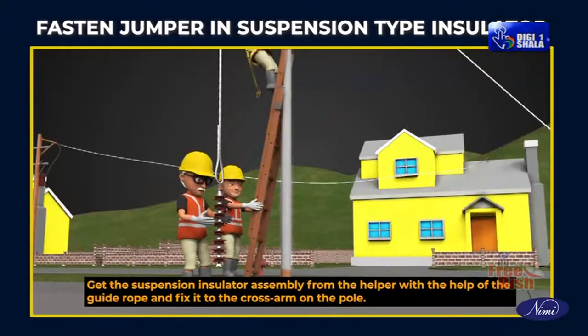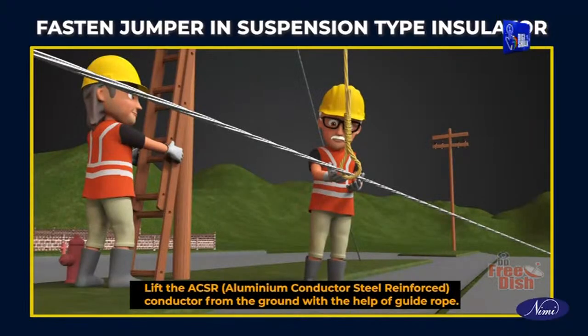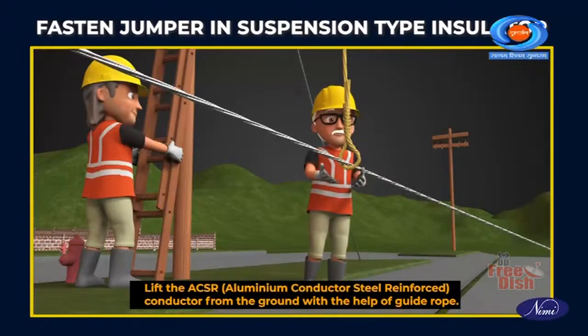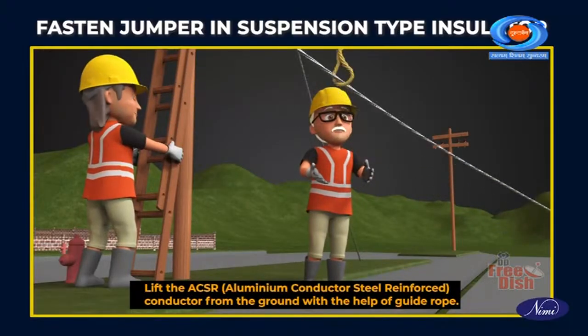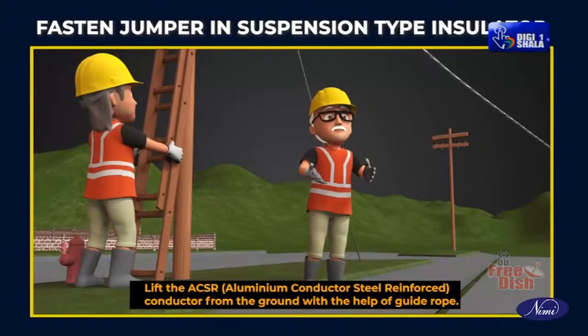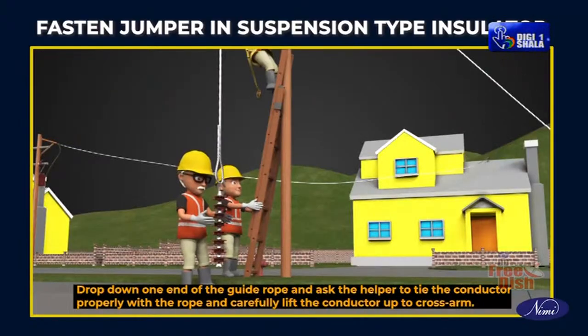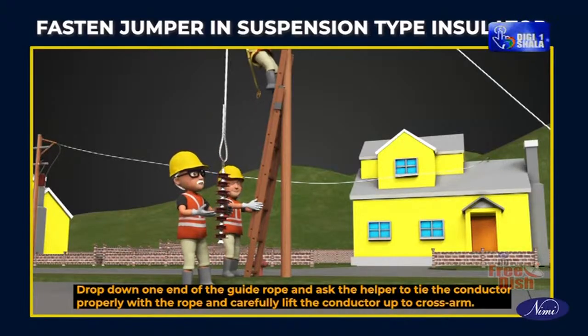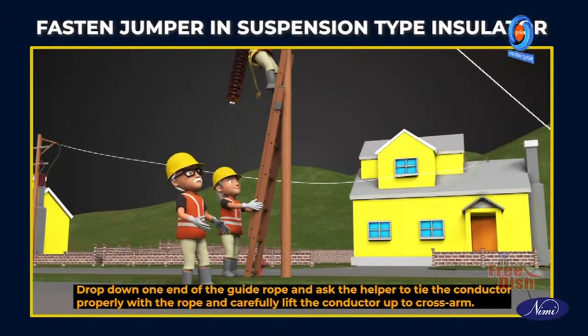Get the suspension insulator assembly from the helper with the help of the guide rope and fix it to the cross arm on the pole. Lift the ACSR conductor, that is aluminium conductor steel reinforced, from the ground with the help of guide rope. Drop down one end of the guide rope and ask the helper to tie the conductor properly with the rope and carefully lift the conductor up to cross arm.